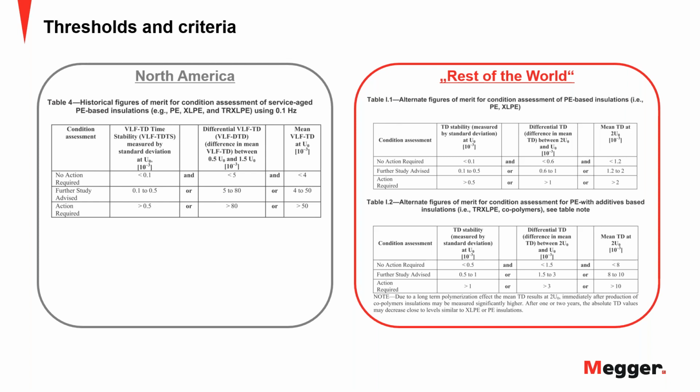But our field expert, who's doing a lot of testing and training with the customers on these issues, told me recently that even they eased up on the criteria because they learned that it's not necessary in their network to take such a rushed and such an early action. So I believe they moved up to 1,000 picocoulomb. But the intention is always the same.